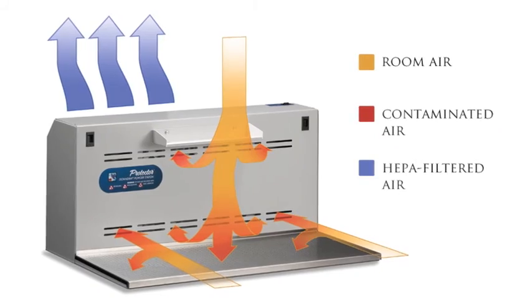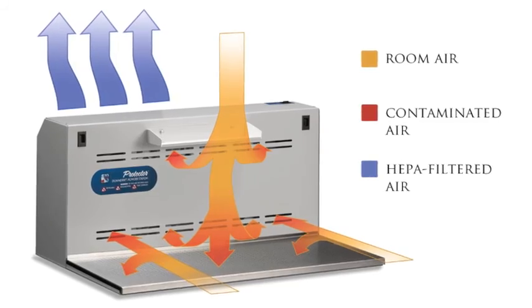The adjustable blower speed can be increased as the filters load to maximize filter life.